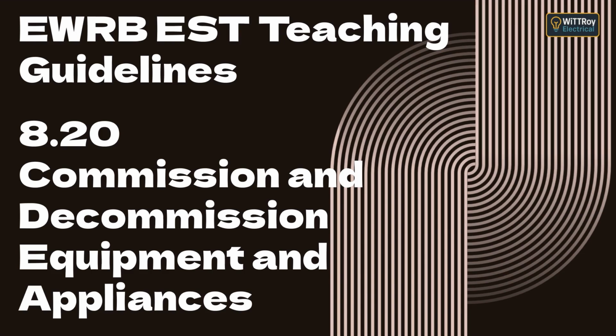Applied example, disconnecting and reconnecting a single-phase pump motor. Let's finish with a practical example that brings topics A to D together. You're servicing a small 230-volt pump motor. You isolate the supply at the switchboard, lock it off, and attach your danger tag. You prove the circuit is dead using prove, test, prove. You mark the active, neutral, and earth conductors with colored sleeves before disconnecting. After completing the mechanical service, you reconnect each conductor to the correct terminal, tighten securely, and carry out 3 tests.